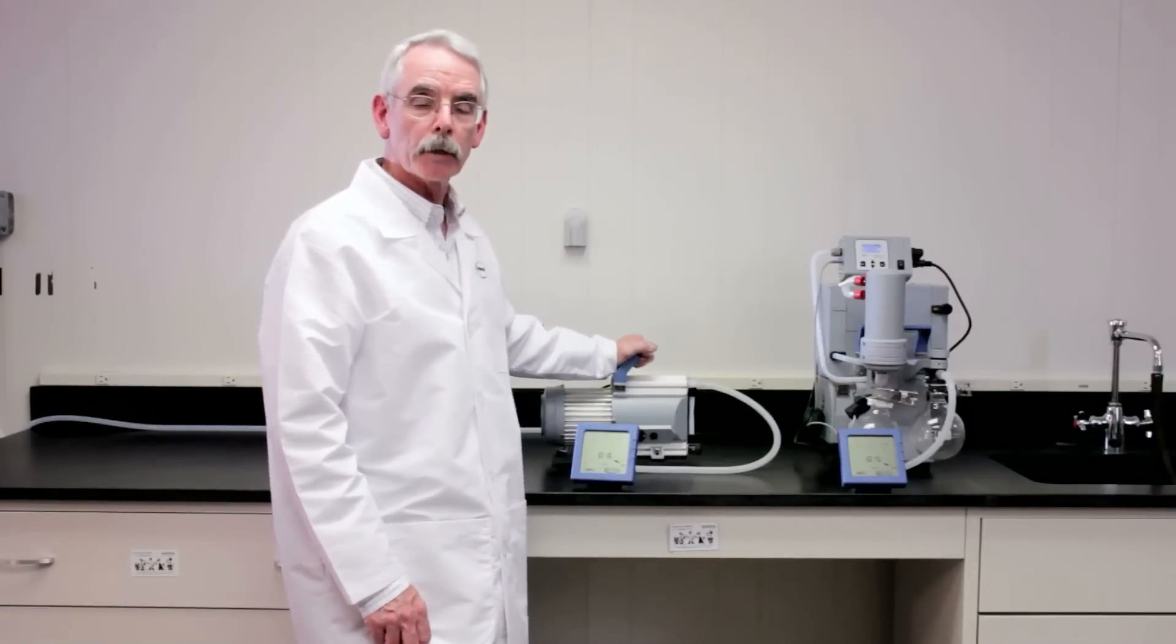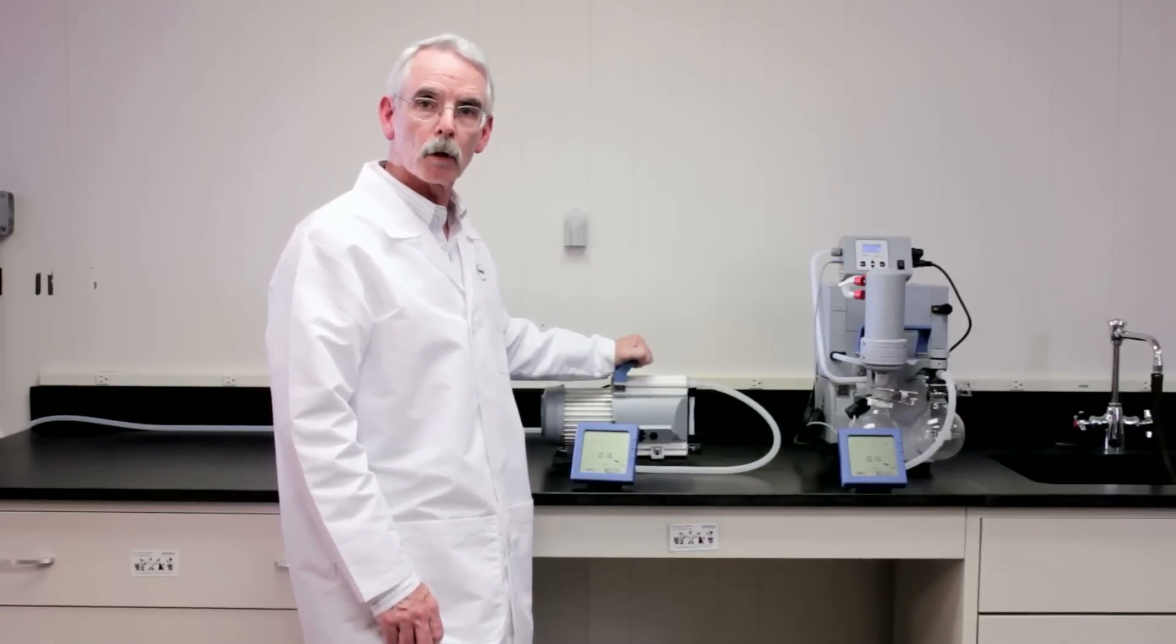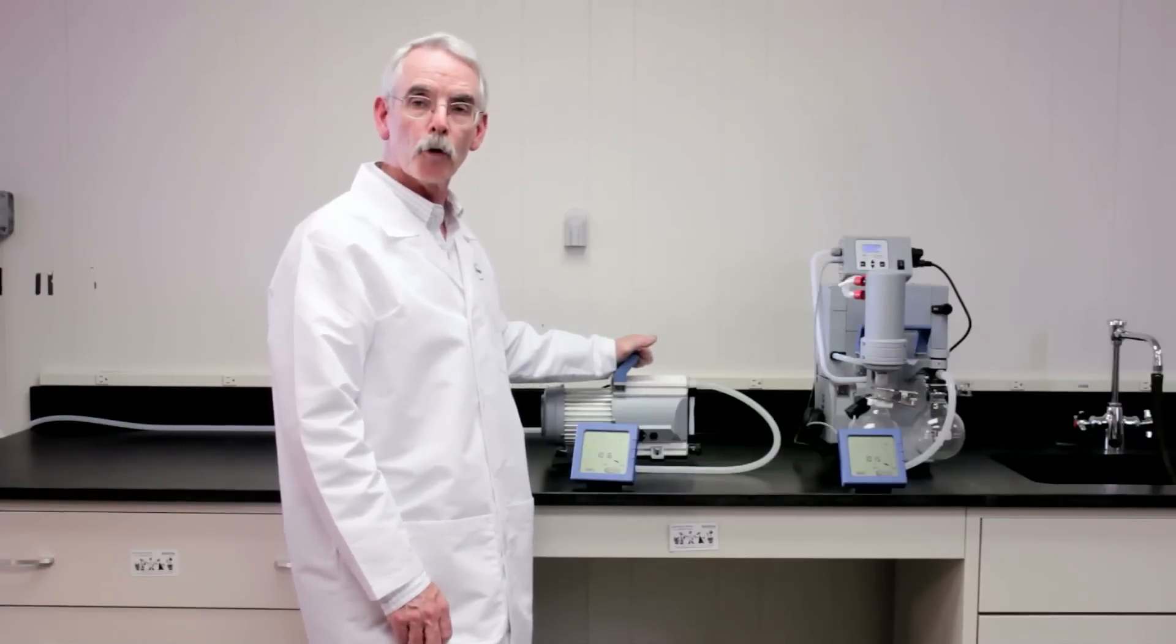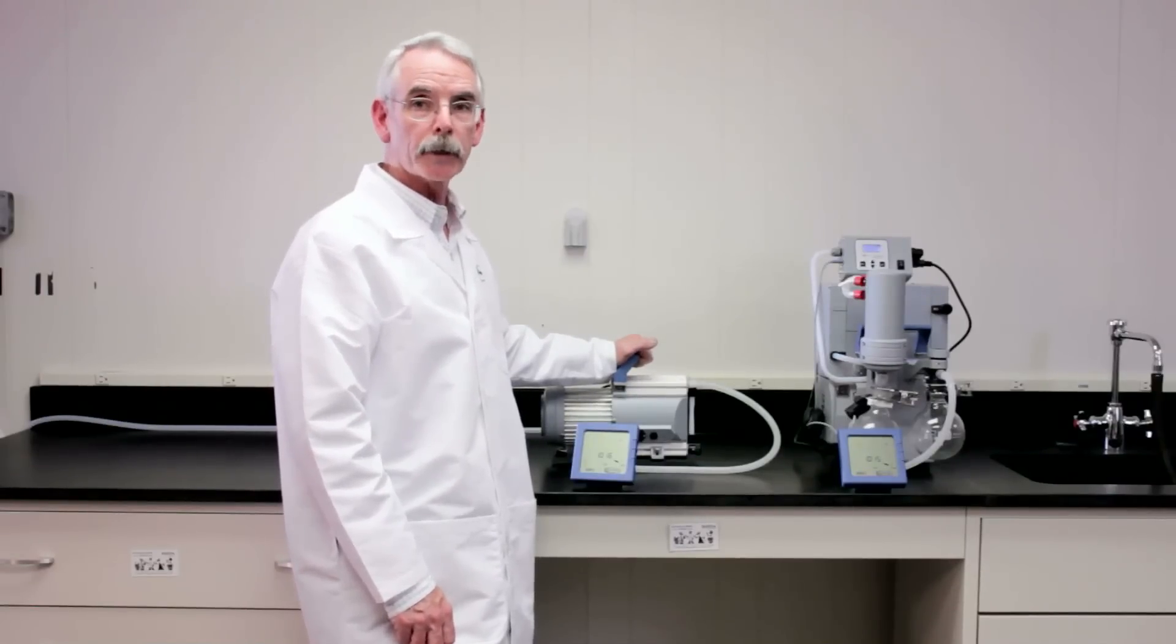Our second pump is the MD1C. This is a compact little workhorse pump with a 5 inch by 10 inch footprint that will deliver 2 millibar vacuum, that's 1.5 torr, 29.86 inches of mercury.